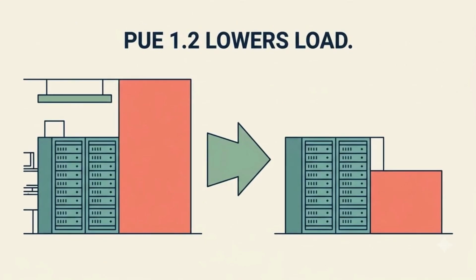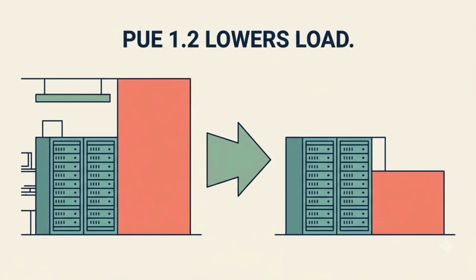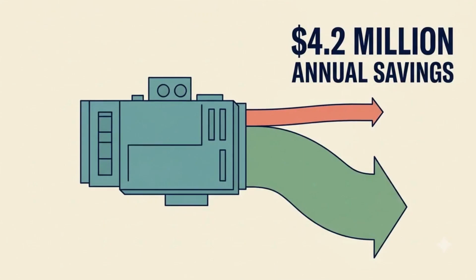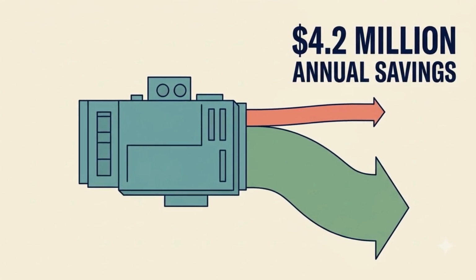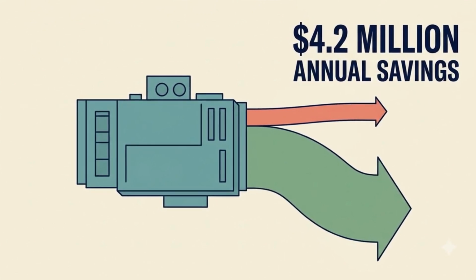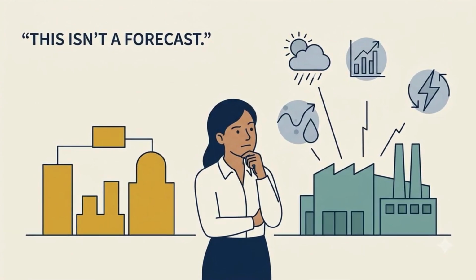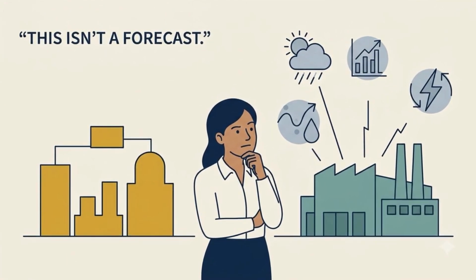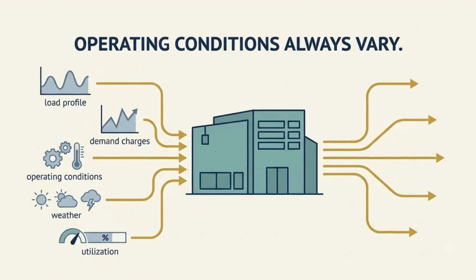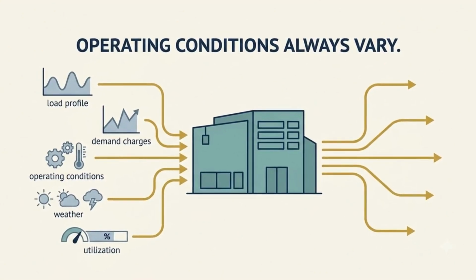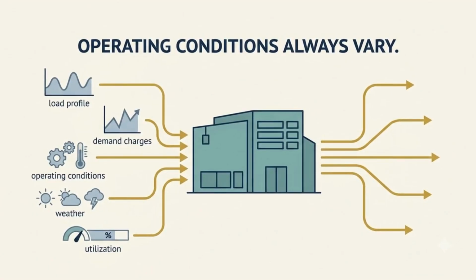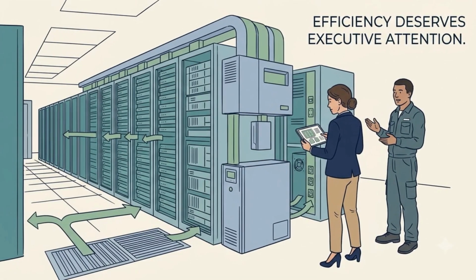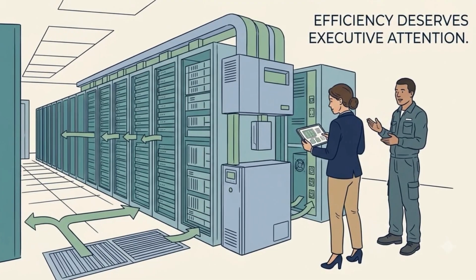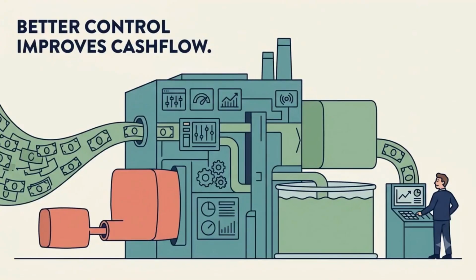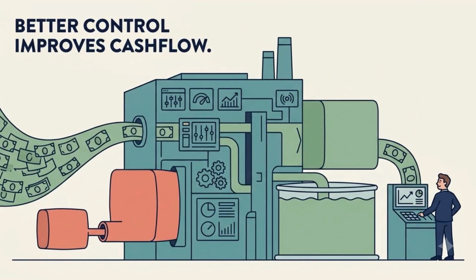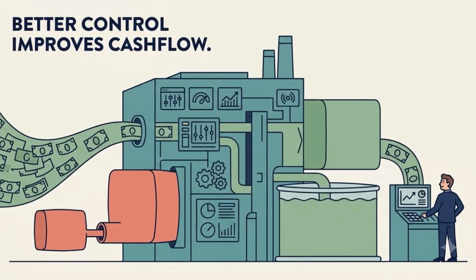If improvements reduced PUE to 1.2, total load would fall to 36 megawatts and overhead would fall to 6 megawatts, cutting that modeled overhead cost by about $4.2 million annually. That is not a forecast for Maya's real facility, because power prices, utilization, load profile, demand charges, and operating conditions vary. It is simply a demonstration of why efficiency deserves executive attention. A better cooling design, more efficient power conversion, improved airflow, or better operating control can materially change cash flow when multiplied across tens of megawatts.